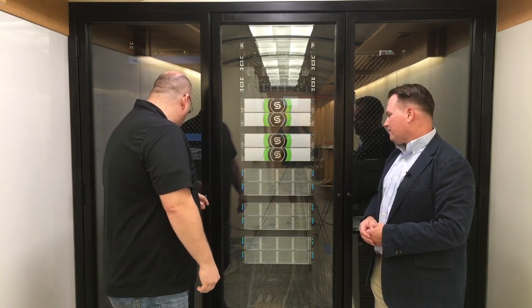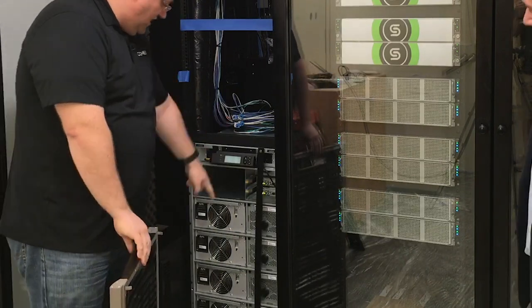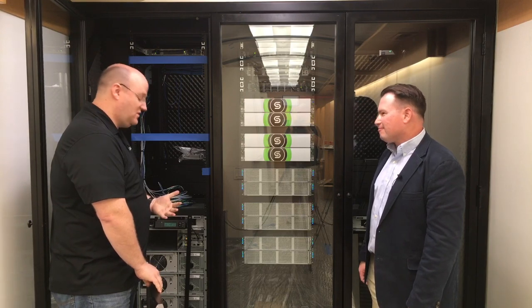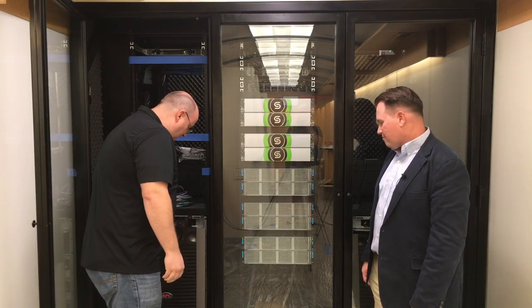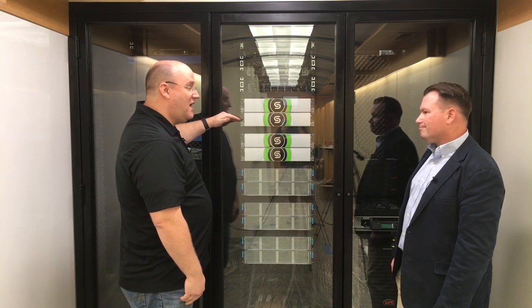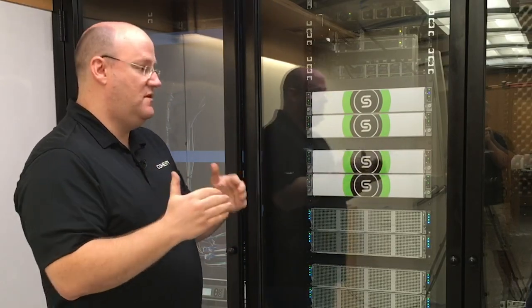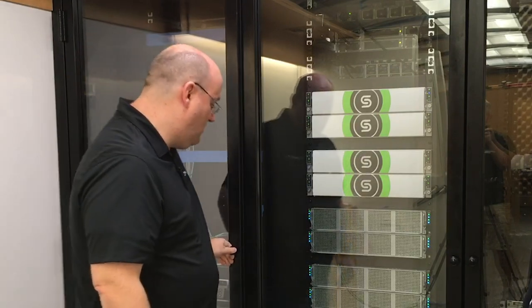Well, one of the gentlemen on my team, Chris Colati, has an RV. If you have an RV, you remember one of the first things you have to do is secure everything before it goes in motion, so we had to put the same principles in here. On our battery units, we've actually put some special bars in front to keep those battery units from sliding out for any particular reason. At the same time, we've done a lot of reinforcement within the rack to keep things from bouncing up and down under that amount of stress going down the road. These are full-fledged metal devices keeping not only the rack from bowing out, but also keeping the things above and below from bouncing around. You wouldn't ever figure when it comes to a data center, you'd have to factor in geological stability as well.